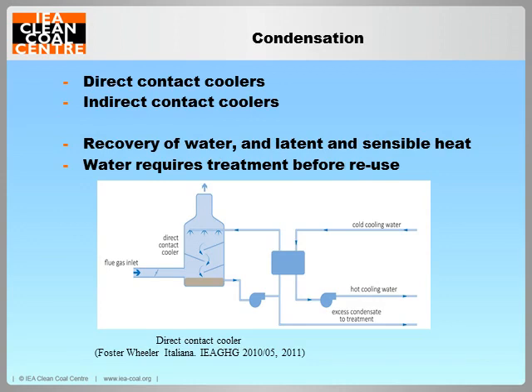Condensation can be achieved with direct contact coolers, where the flue gas and cooling fluid are in direct contact with each other, as shown in this figure. Otherwise, indirect contact coolers could be used when an intervening wall separates the cooling fluid from the flue gas. In both cases, condensed water needs to be treated before it can be reused within the plant.